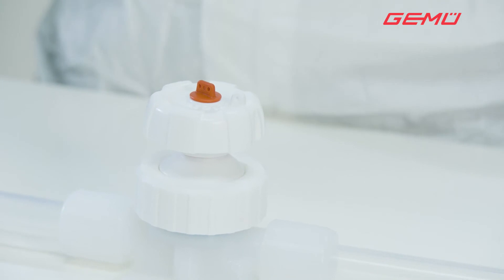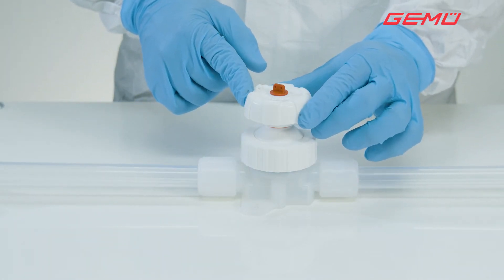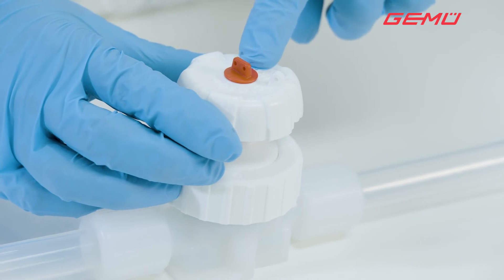Since on a manual valve the mechanical stress of the diaphragm depends on the closing force exerted by the operator, we recommend readjusting the seal adjuster after each diaphragm replacement. To adjust the seal adjuster, the valve must be opened slightly by turning the handwheel anti-clockwise.